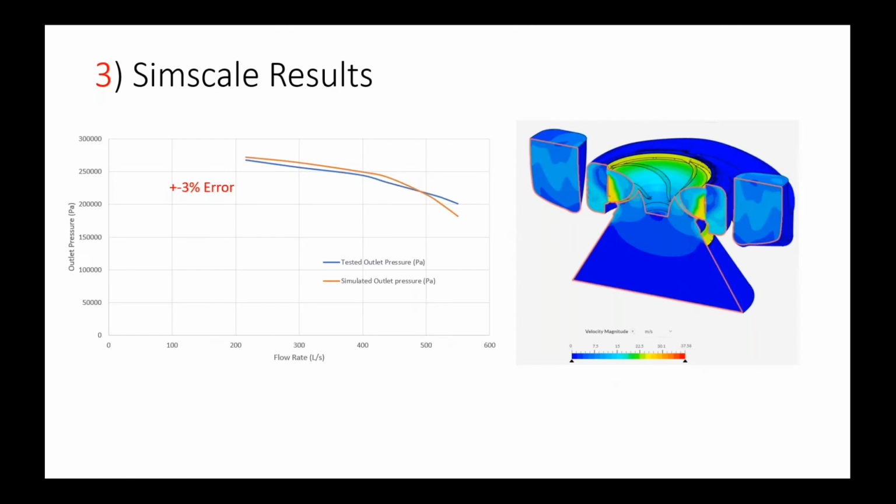And we also plotted the simulation results with what we found from SABS, and we found that we were plus minus 3% within that target. I want to stress this point: just to take the pump to SABS to test it costs about $3,000 per test. If the test results are this accurate, we can do much of that work locally, as opposed to designing, testing, and spending loads of money doing that.